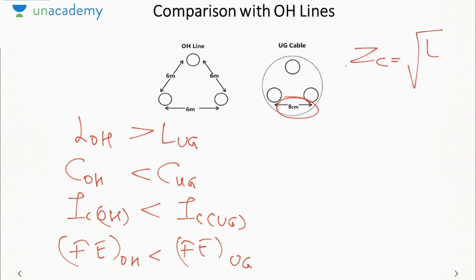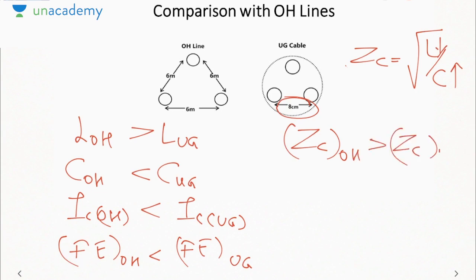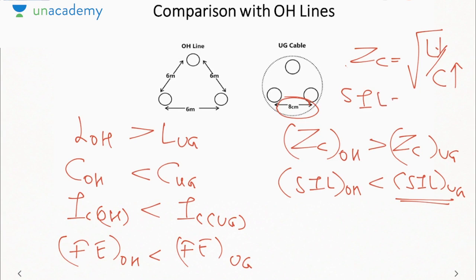ZC is root L by C. So inductance reduces, capacitance increases, so ZC will reduce. So ZC of our overhead line is greater than ZC of UG cable. Surge impedance loading of UG cable will then be greater than that of the overhead line. Surge impedance loading is V square by ZC, so it is inversely proportional to ZC. If ZC reduces, that means SIL will increase. So the ideal power transfer capability of a UG cable is more than that of an overhead line.